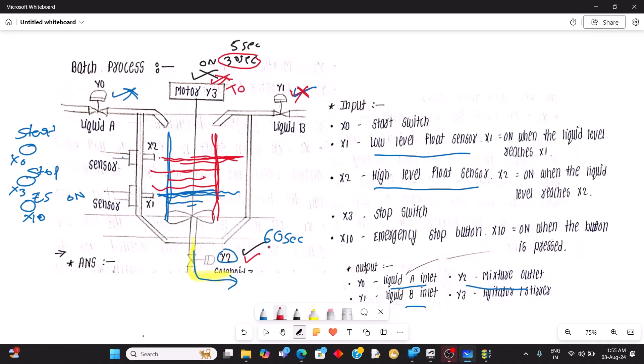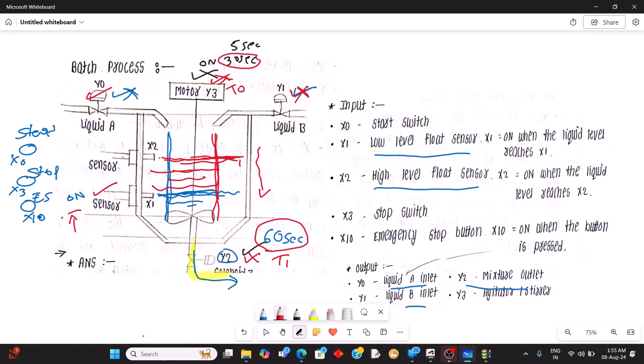After 60 seconds — using timer T1 — we turn off Y2. But think about these sensors during the draining out: they will remain in the on state. Because when X1 is high, Y0 is being triggered again. So instead of using these sensor bits directly, we can use the rising edge trigger. We'll see this in the program — first we develop without the rising edge and see how it works, then we'll introduce the fix.